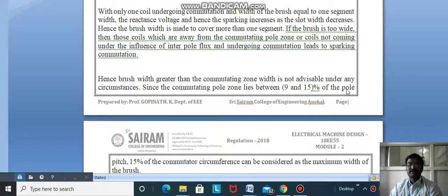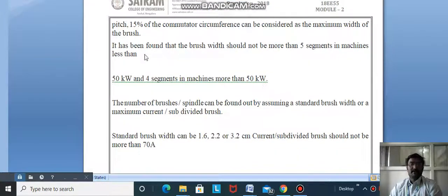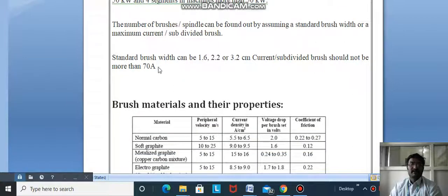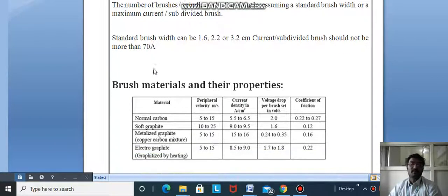It has been found that brush width should not be more than 5 segments in machines less than 50 kW, and 4 segments in machines more than 50 kW. Standard brush width can be 1.6, 2.2, or 3.2 cm. Current per subdivided brush should not be more than 70 amps.